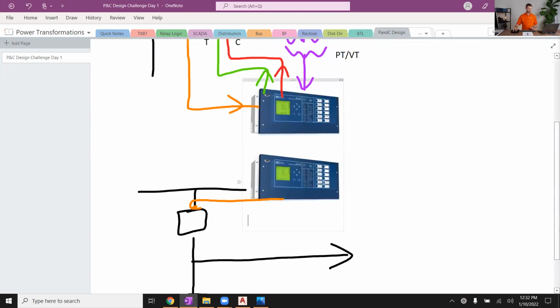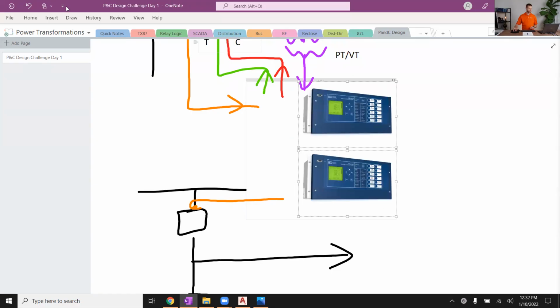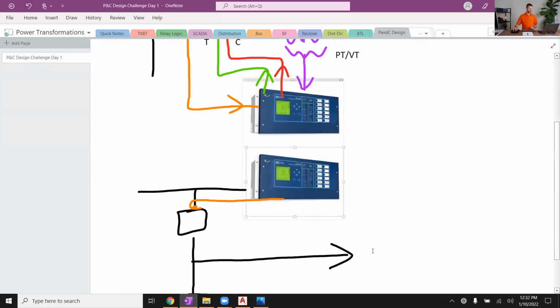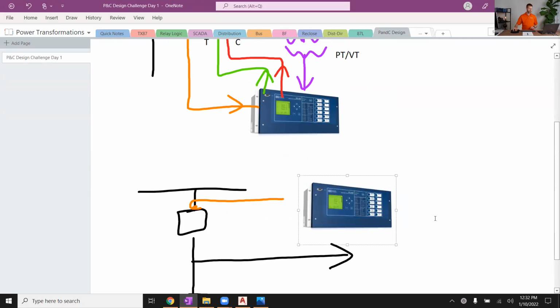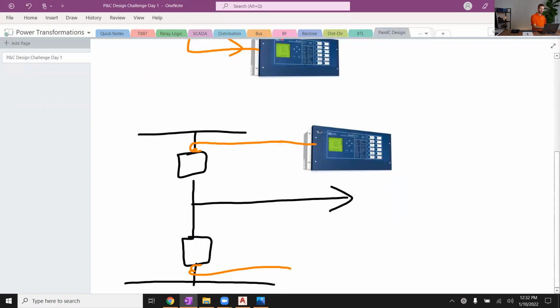And then I'd put the relay in here. Let's copy this down. Oh, undo. There we go. That's good enough. And so we bring in our CTs separately to this W and to this X current terminal on the back of the relay. We call that W and X. So hopefully you can see that. That's a double bus, double breaker. The same would be true if you had a breaker and a half with 3 breakers in the line bay. The same would be true if you had a ring bus, which has 2 breakers on a line.